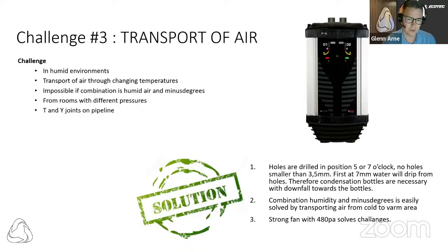Another challenge can be the transportation of air in humid environments, through changing temperatures, in combination with humid air in minus degrees, from rooms with different pressures, and T and Y joints on the pipeline. And the solution from Elotec is that the holes are drilled at position 5 or 7 o'clock, and no holes are smaller than 3.5 millimeters in harsh environments, because first at 7 millimeter holes, water will drip out from the holes by itself. Therefore, condensation bottles are necessary with downfall towards the bottles.